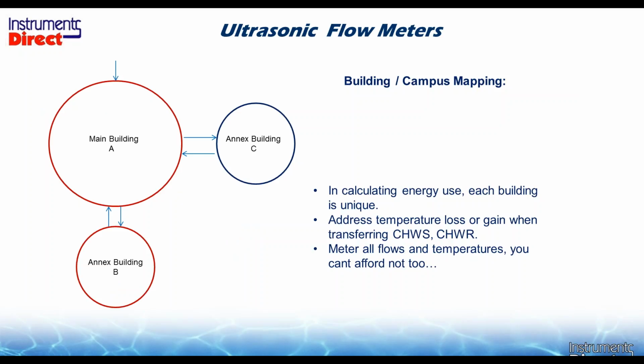Another mismatch that's commonly happening in energy management is assumptions. Everybody thinks the square footage for one building to another will have the exact same energy cost. So in this case, main building A manufactured the chilled water and basically transferred it to building B and building C, and they return it back. When the energy costs were monitored, we noticed that Annex Building B had lower energy costs than Annex Building C, and we couldn't figure this out. They were both the same square footage, the same personnel, the same operation. Everything was the same. So we went out and did a study.